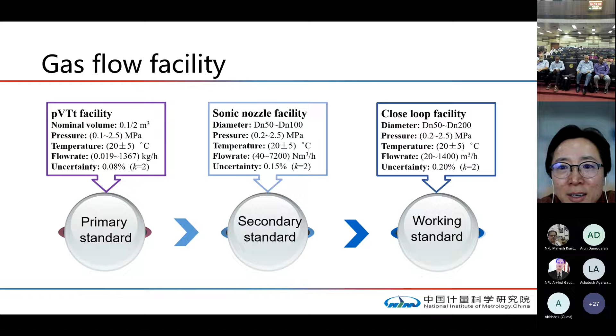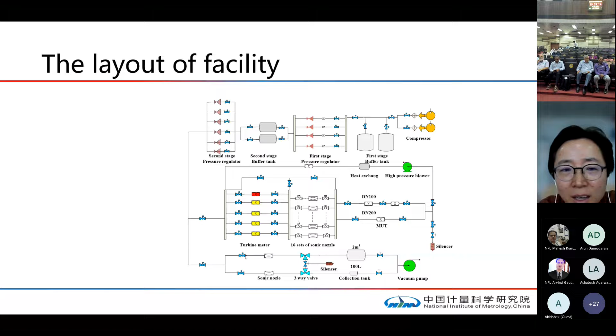Our high pressure gas facilities consist of 3 facilities, including the Pvtt primary standard and a sonic nozzle secondary standard and closed loop working standard. The turbine meter as the mass meter in the closed loop facilities. This is the layout of our facilities. The high pressure facilities use the same compressed air as the supply, as the source of the system.